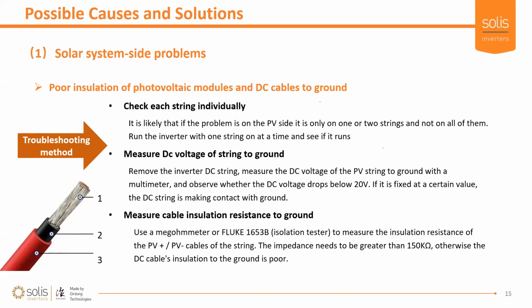Probably the most common occurrence of this is broken DC wire insulation. The insulation is points 2 and 3 in the figure. If this is broken or cut into, there will be no problems immediately, because air is in fact a very good isolator. So you, in theory, could have just the cut running along the system, but if anything does touch it, and obviously things are floating around in the air and things can touch it easily, you will run into a lot of problems. So yeah, air is a very good isolator. However, if any conductors connect to earth, or come close to it, it would cause this issue. This often happens at 90-degree turns for steel trunking, where the edge forms a sharp edge, and generally the trunking is earthed. So when that cut is made, the steel makes a good connection through to the conductor in the middle of the wire, and it causes a nice, strong connection through to earth.